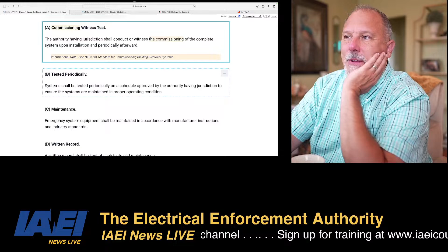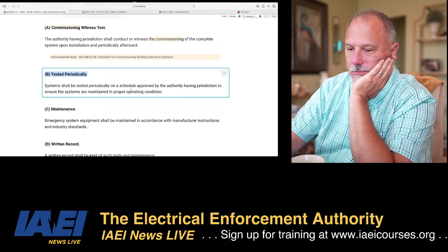700.3, I think we just talked about, right, Daryl? Daryl Hill, 700.3. 700.3 is test and maintenance. Commissioning witness test: the authority having jurisdiction shall conduct or witness the commissioning of the complete system upon installation and periodically afterwards. Well, let's look at 700.3. It says, tested periodically, Daryl. Systems shall be tested periodically on a schedule.